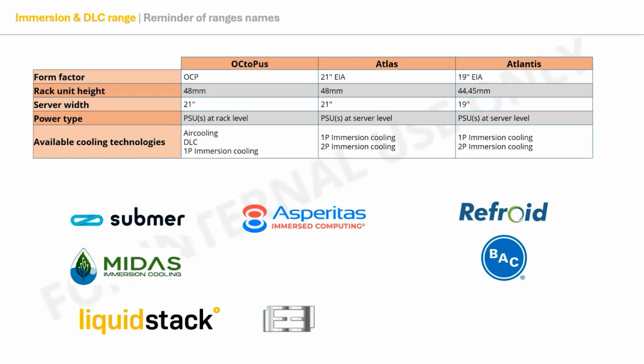In Atlas, you have the PSU at the server level, as shown in the power type. In Octopus, it's at rack level. What I call rack level is that you have a power shelf connected to the bus bar, and the bus bar distributes the power to the servers. That's the technical difference between these two types of product.